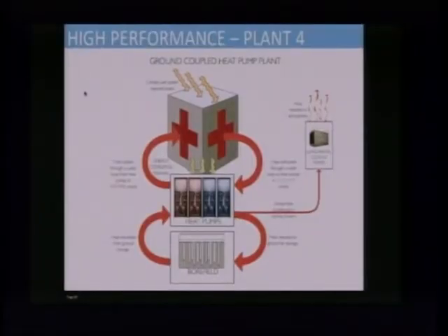So the fourth plant, Plant 4, the third high performance plant, is the ground coupled heat pump plant. At the core, essentially the ground serves as a battery. It holds heat, or you can extract heat depending on what the hospital needs. There are central plant heat pumps, and the ground can be bypassed. If there's excess heat in one place of the hospital and need for heat in another place, it'll just go through the heat pump and be a circular system, bypassing the ground.